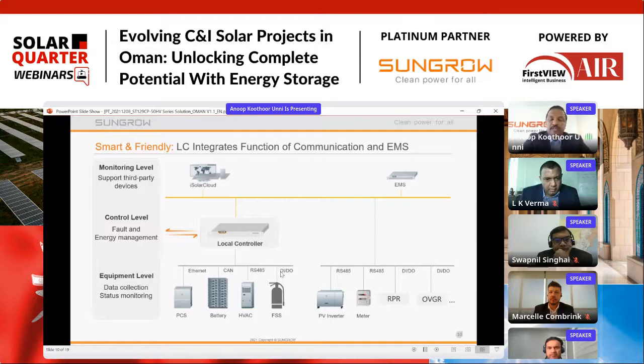Now, when we talk about product integration with the PV industry, for C&I products, especially for the BESS, along with the supply, this will work as an off-grid system. But when we're talking about renewable sectors, it always needs to be connected with the PV plant. The communication is a Modbus protocol if available, so the local controller and EMS can communicate with COM100, and all details can be monitored through iSolarCloud mode. In this case, PCS, battery, HVAC, and firefighting will be monitored through the local controller, whereas the PV inverters and energy meters or any kind of relays can be monitored through the EMS.